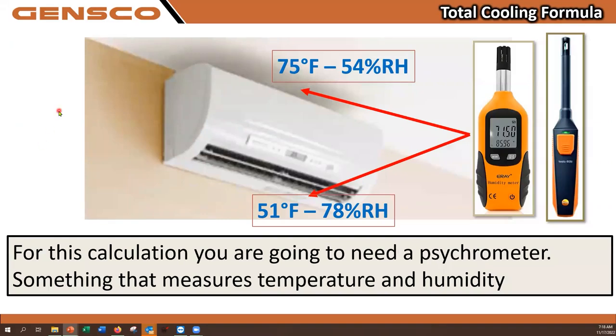Now, to do a total cooling, you're going to need more than just a thermometer. You're going to need something that can also measure humidity or wet bulb temperature, something that can tell you the actual conditions of the air. And we're still doing an MSZ, MUZ system. These are the results we got using a psychrometer. 75-degree return air at 54% relative humidity. And our supply air was 51 degrees with a 78% relative humidity.